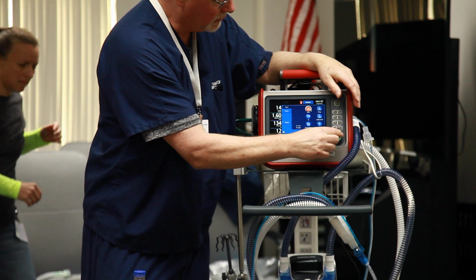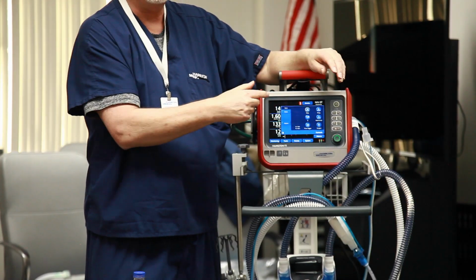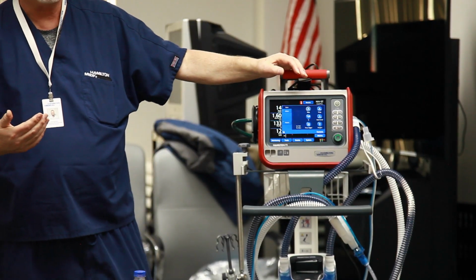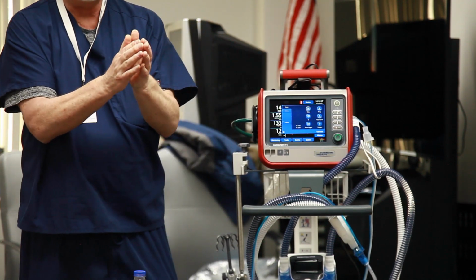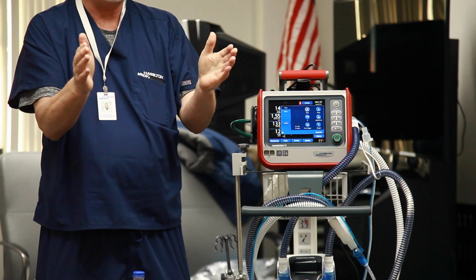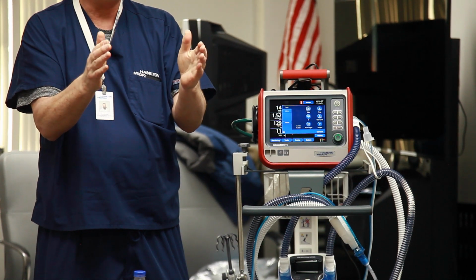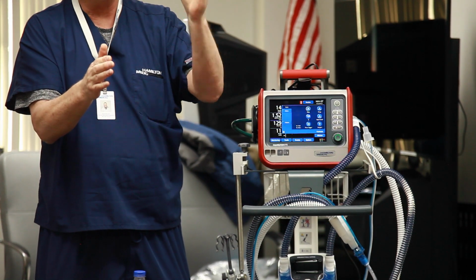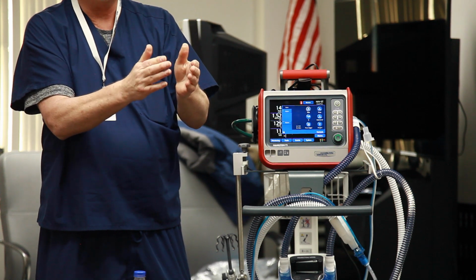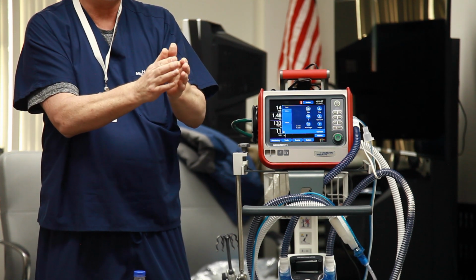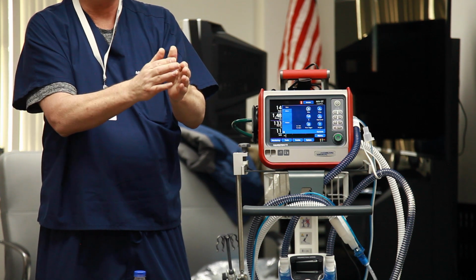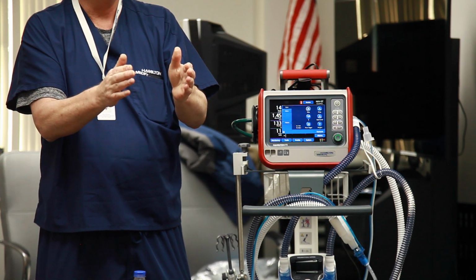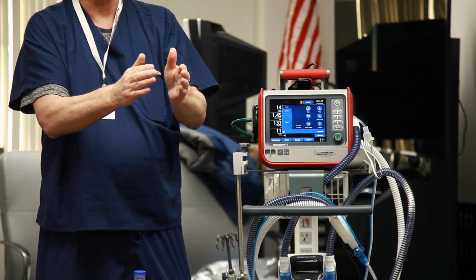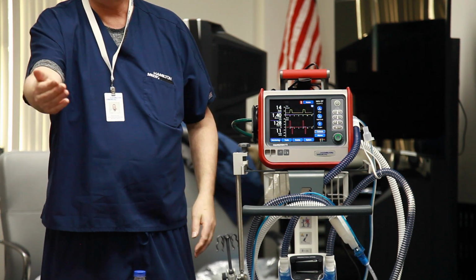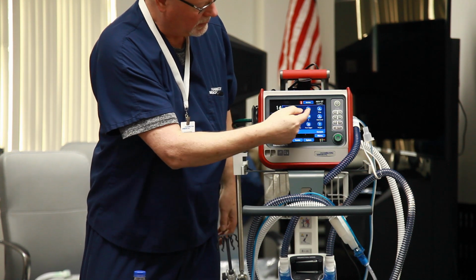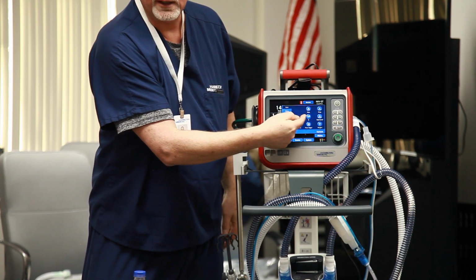So how this works, I'm going to do this at a rate of 10 because it's just really easy math. So with the rate of 10, you have a cycle time of 6 seconds, right? 60 seconds divided by 10 is 6 seconds. So you give a breath, and then it's looking at a 6 second window. If there's a breath that's taken, it just starts that all over again. But if there's not a breath, then it gives a breath at the pressure and the inspiratory time we have set.